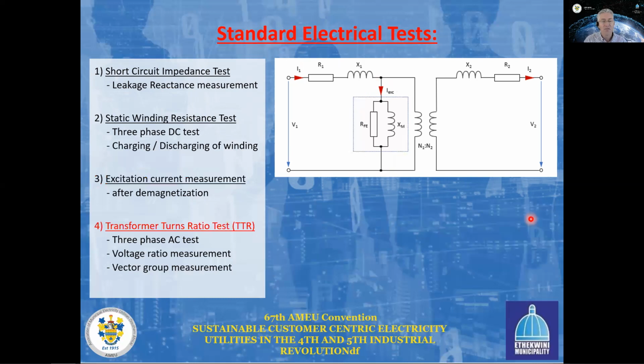And then we have the transformer turns ratio measurement on a transformer, typically referred to also as the TTR. This is also a 3-phase test. Why a 3-phase test? Because it was just quicker. You can do all 3 phases at the same time.